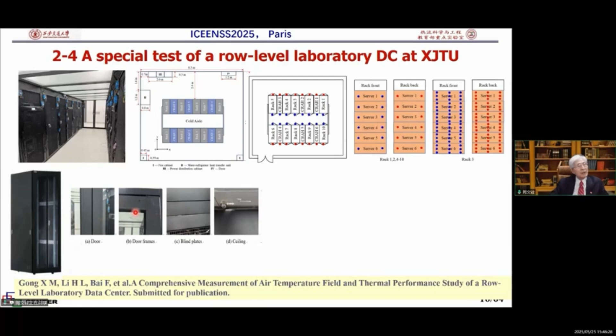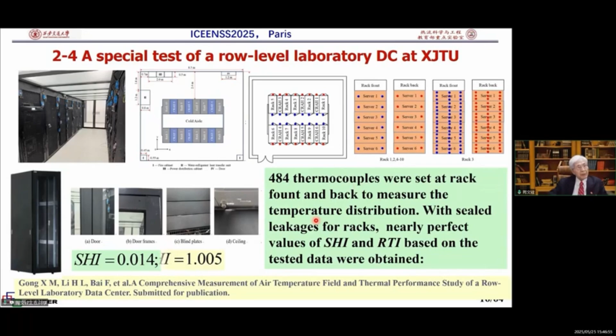Then we made a very comprehensive measurement of the air temperature. Totally 484 thermocouples were set at the rack front and back to measure the temperature distribution. With this kind of test, we got the room SHI almost equal to 0.014, and the RTI almost equal to 1.005.